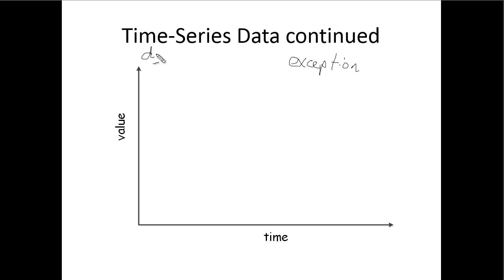Okay, so I have my device and I poll it. Okay, so I'm doing my poll. And I'm getting back my values. I'm getting back V1, V2, V3. And like I said, I'm doing this every 250 milliseconds, right? So I'm taking a bunch of readings. All right. But what I do is I look at these readings as they're coming into my system, and I say, well, you know what? If these two values are the same, I don't need to store every one of them.